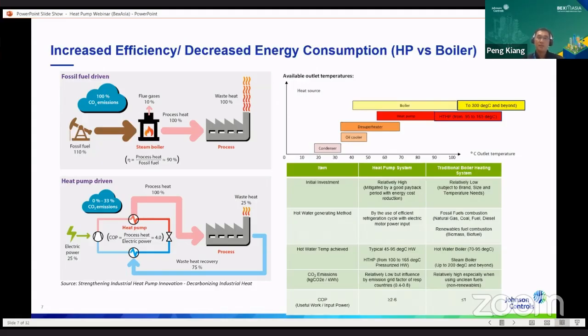But of course, if you look at heat pump technology versus boilers today, a boiler is almost an unparalleled means of creating high heat at any pressure and temperature that you can imagine. Versus that, a heat pump has certain limitations. It will be able to create hot water today perhaps up to 95 degrees C as a standard product. But we are moving towards more exploratory territory where we can create heat pumps up to 120 degrees C hot water, or even 165 degrees hot steam, depending on the products that we're using. That's about the limit of the heat pump.